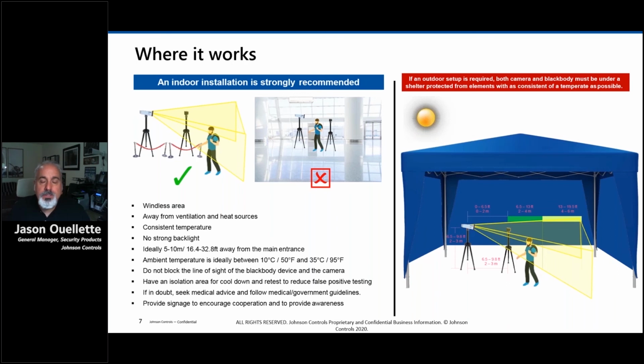One thing I would summarize here is that while the solution can be used outdoors, there are a lot of considerations because of the thermal influences. You'd want a tent covering and walls to protect from draft and sunlight, and you need to make sure you still get the proper distancing away from the opening of the tent to protect from drafts and other things that can influence accuracy. But the solution can be deployed on tripods, made quite portable to move around. So it can be in one location in the morning when everybody's coming in, and then at lunchtime you move it towards the cafeteria and do a recheck without having to buy additional devices. It's not that complicated to move this, do a quick calibration, and be up and running. So there's some good flexibility there.